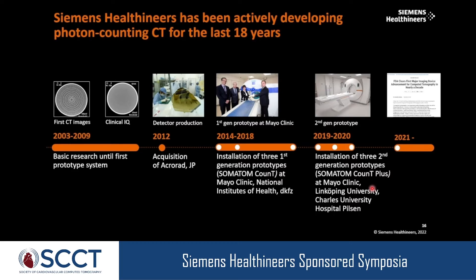The development of photon counting CT at Siemens has been ongoing for almost 20 years, starting in 2003 with first images and achieving clinical image quality. In 2012, Siemens acquired the company Acrorad, which had the cadmium telluride detector material. Prototypes were installed at the Mayo Clinic, NIH, and the German Cancer Center; a second generation came in 2019; and in 2021, FDA 510k clearance was granted — described as the first major imaging device advance for CT in nearly a decade.